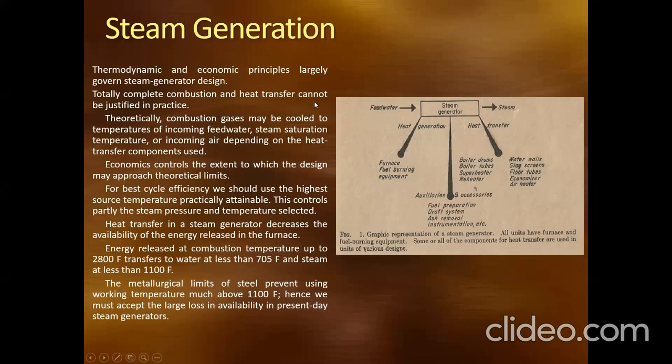So, thermodynamic and economic principles largely govern steam generator design. Totally complete combustion and heat transfer cannot be justified in practice. Theoretically, combustion gases may be cooled to the temperature of incoming feed water, steam saturation temperature, or incoming air, depending on the heat transfer component used. Okay? So economics controls the extent to which the design may approach the theoretical limit. So for best cycle efficiency, we should use the highest source temperature practically attainable.